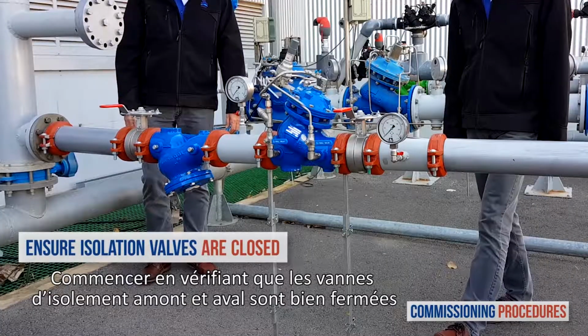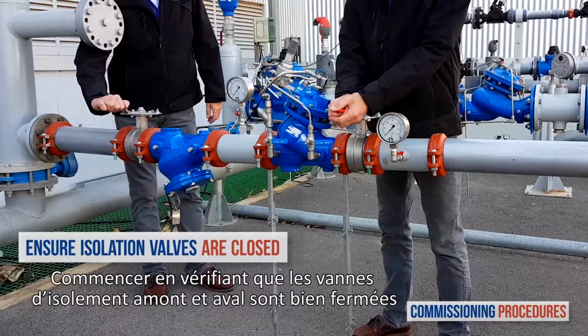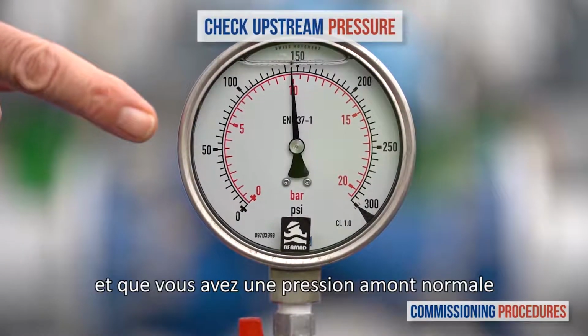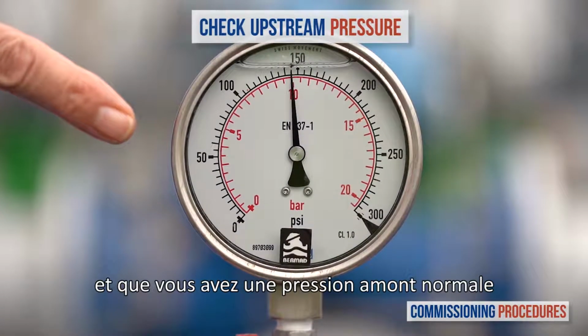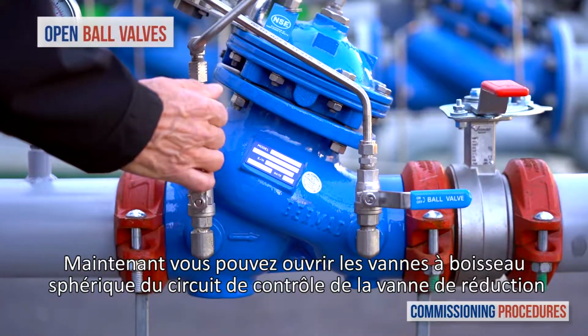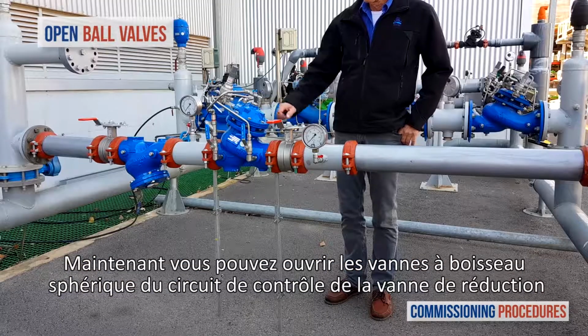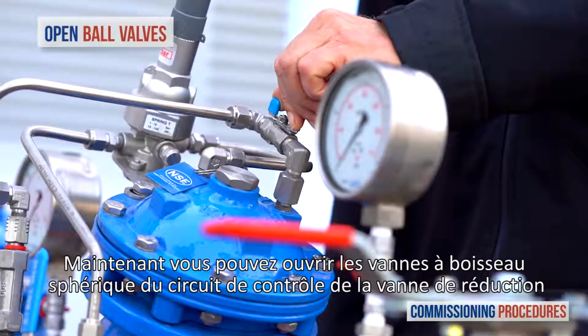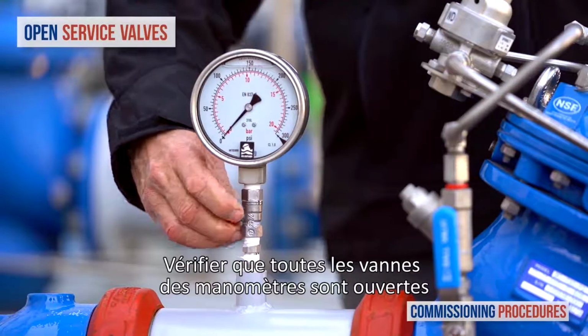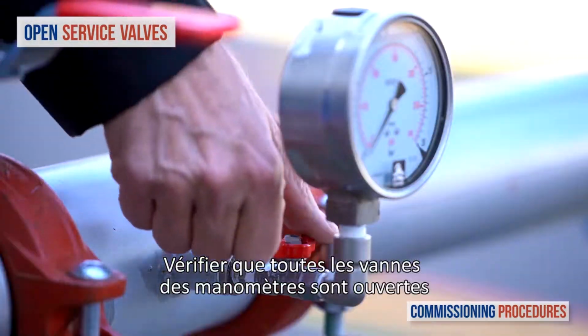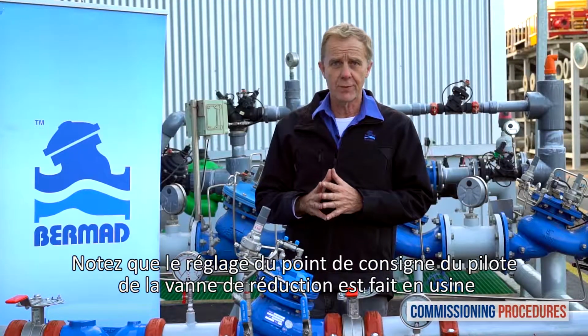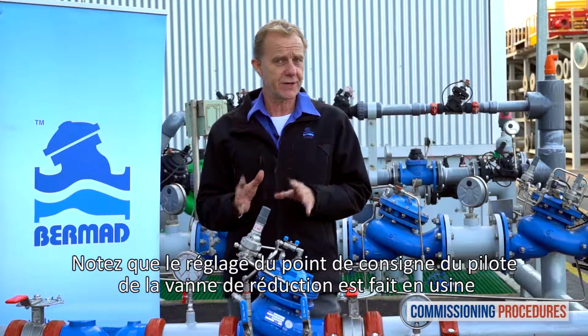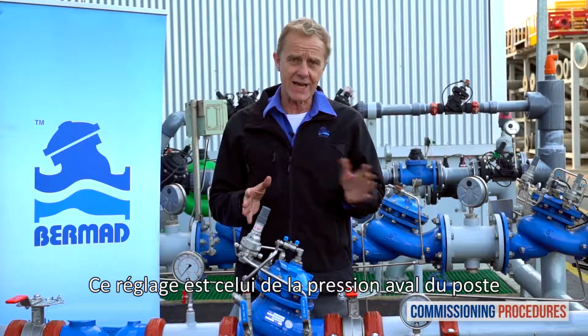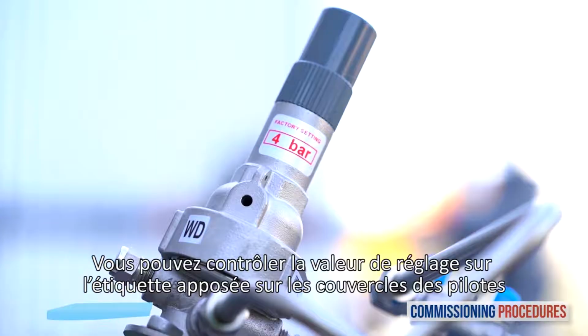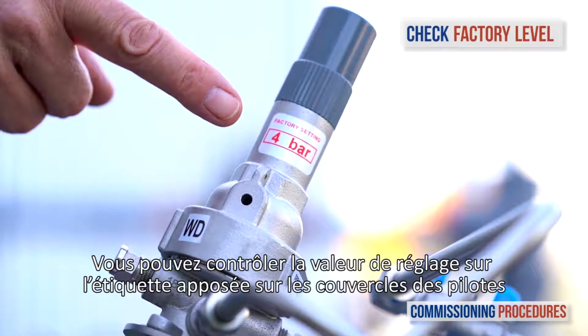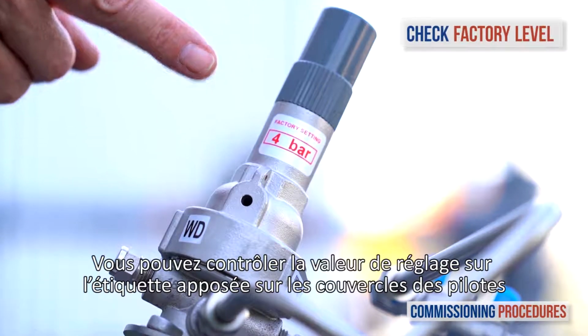Proceed by verifying that the upstream and the downstream isolation valves are closed and that you have a typical upstream pressure. Now, open the ball valves at the pressure reducing valve's control trim. Make sure that the service valves on all the pressure gauges are open. Note that the pilot level of the pressure reducing valve has been set at the factory. This level is the set downstream pressure of the station. You can check the factory level by reading the label on the pilot cover.